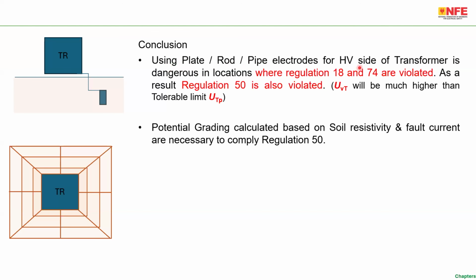Using plate, pipe, rod in HV side of the transformer is dangerous in locations where regulation 17 and 18 and 74 are violated. As a result, since you are violating regulation 18 and 74, regulation 50 is also violated because there is no metallic fault return path. UVT will be much higher than the tolerable limit UTP. As a result, people get shocked. Potential grading calculated based on soil resistivity and fault current are necessary to comply with regulation 50.